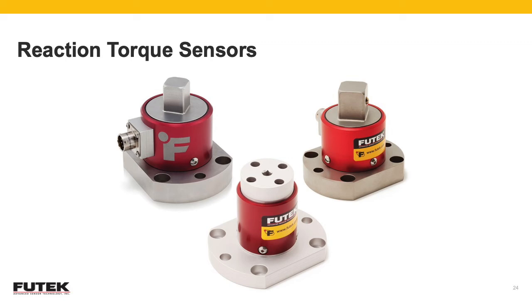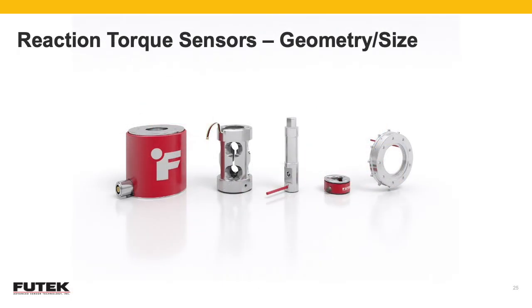One feature that is possible with reaction torque sensors is overload stop. This is basically built-in protection to help ensure that the torque sensor is not damaged if too much torque is applied. As I mentioned a moment ago, geometry is one factor at play with reaction torque sensors.